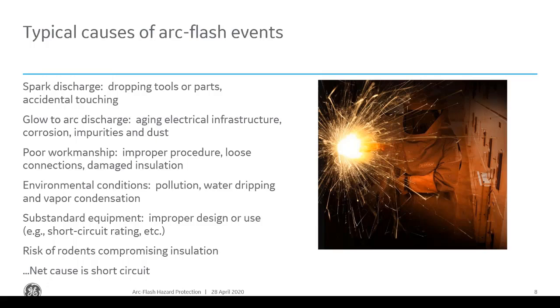Improper design and improper equipment selection can also increase arc flash incident energy. For example, if you have a slow breaker and not a fast breaker, obviously the longer the breaker takes to operate and clear the fault, the longer the arc flash energy is sustained. And obviously, if you haven't sized your conductors and buses properly, that can lead to more insulation breakdown over time.